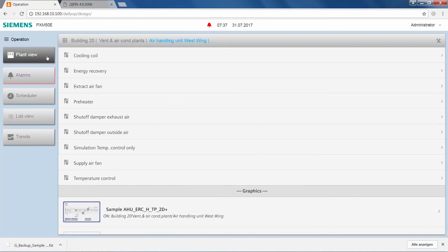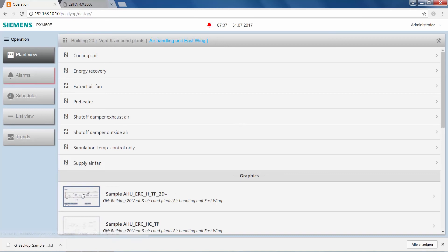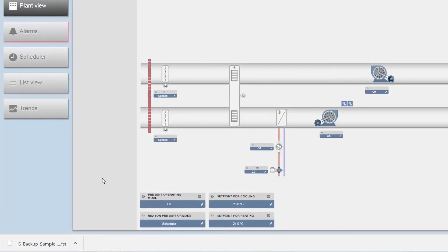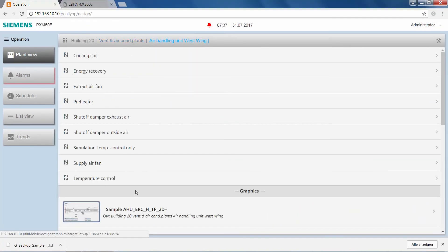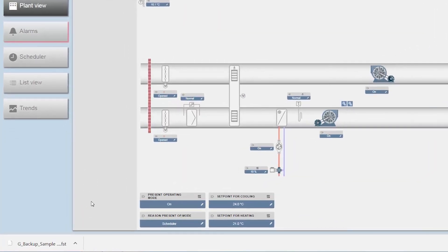Once we have done that, we go back to the operator screen to verify the functionality. We go back to Plant View, Ventilation and Air Conditioning Plants. We drill down first into the east wing air handling unit and open the graphic there. Once the graphic has opened, we see that its label for the cooling set point shows 25 degrees. Doing the same for the west wing air handling unit and opening the graphic there, we see that the label for the cooling set point shows 24 degrees, as we expected.